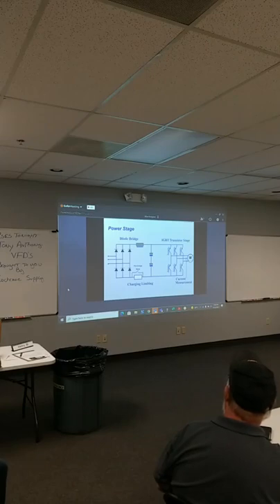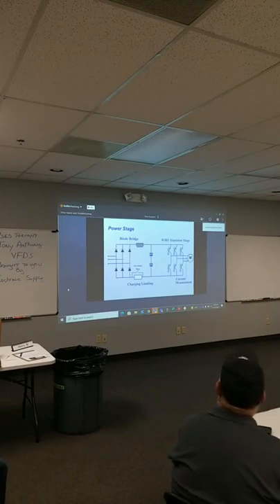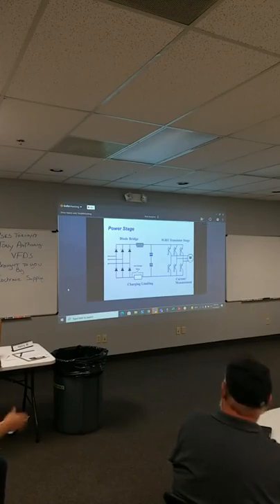Once again, an ohm meter is a very simple way to check your diode bridge, which creates our DC bus. If you're having a problem on your DC bus and you don't see the voltage you think you should see, check the diodes. That way you can see if you've got a problem with the pre-charge system or with the diode bridge.